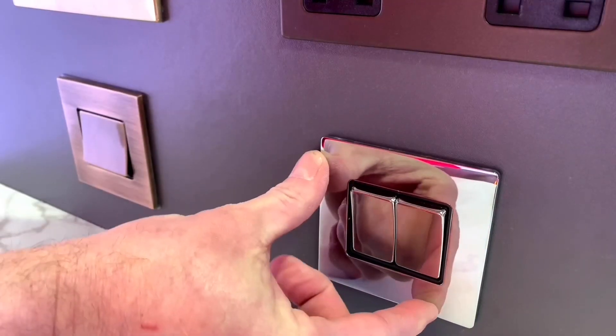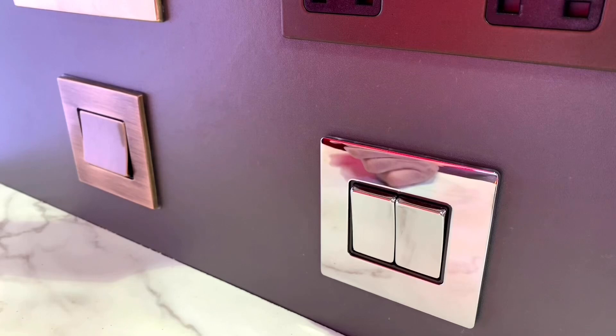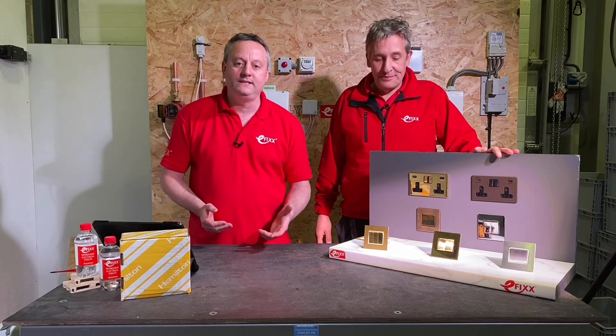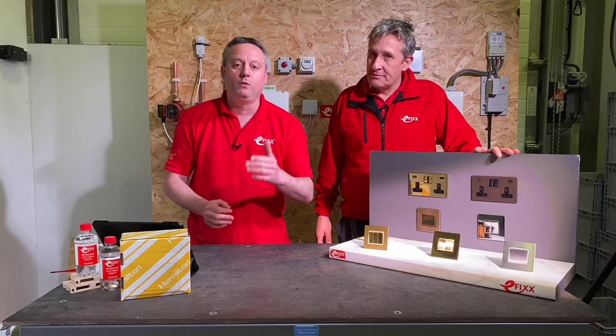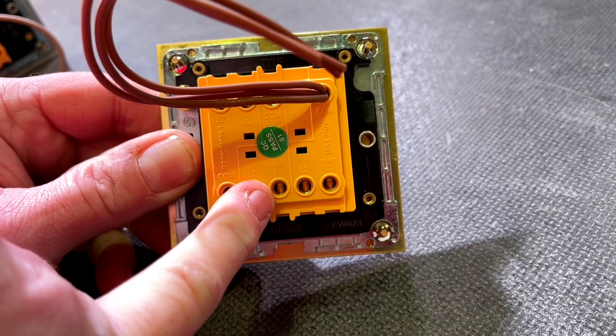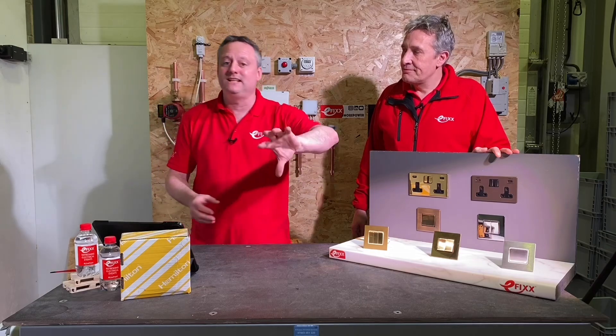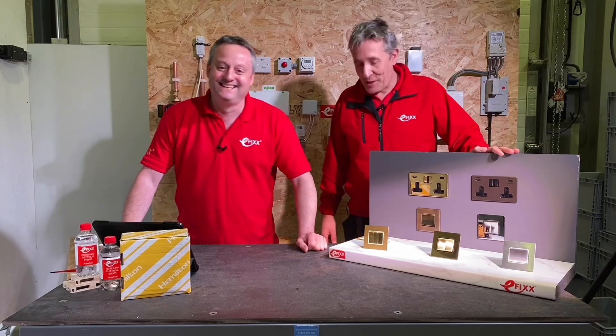There's obviously going to be a screwless front to this, and there is something very satisfying about clipping into place the front antique brass plate once you've levelled up your box. The Hamilton plates are very easy to clip on and remove — something we've struggled with on other brands where you end up nearly wrenching the switch off the wall to get the decorative plate off. The one-gang two-way switch clearly identifies the one-way element, as it does on the two-gang and three-gang switches, making it so much easier so you're not going back after testing to rotate it or move a conductor. Sounds like personal experience there!